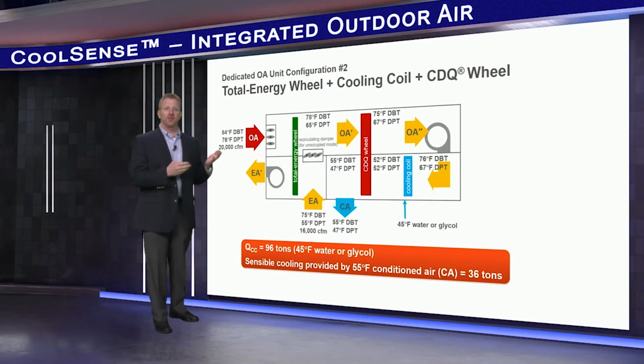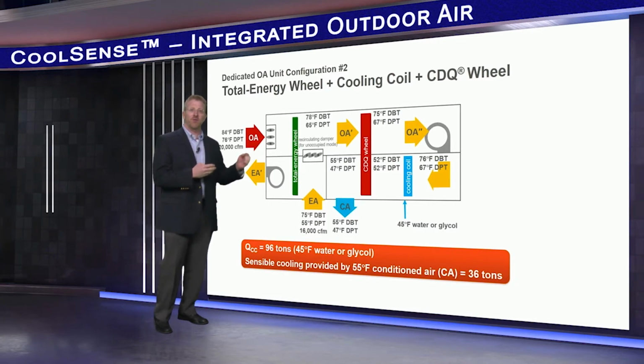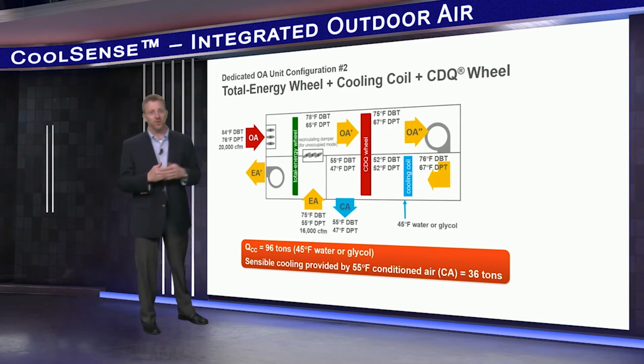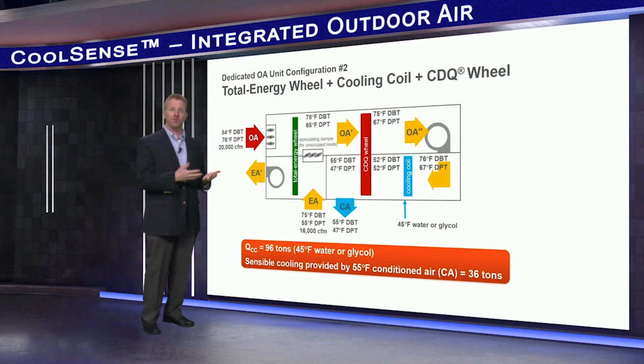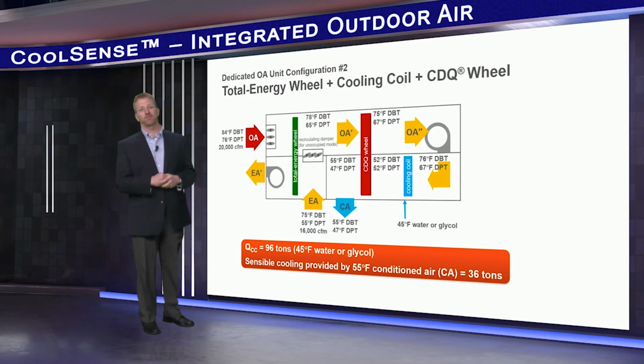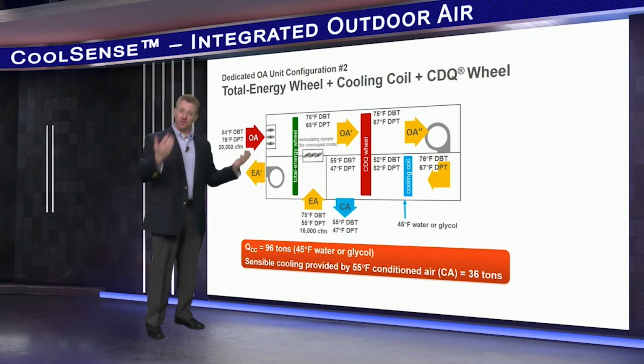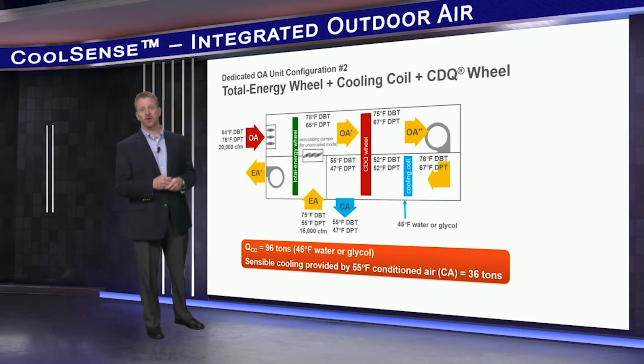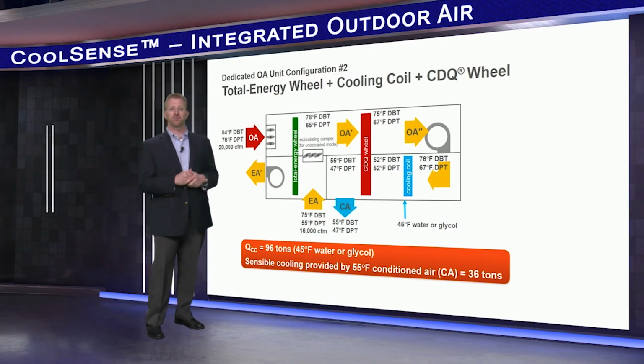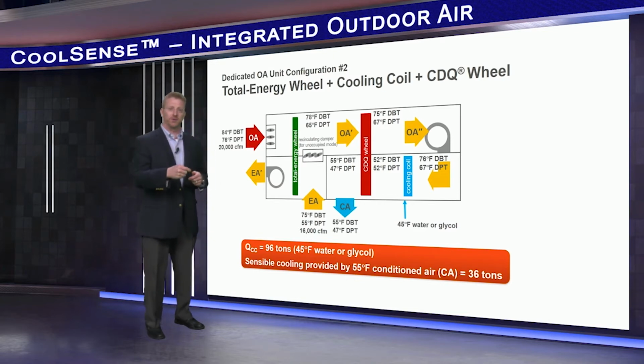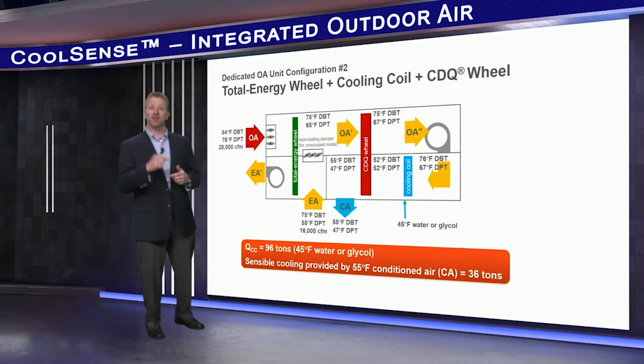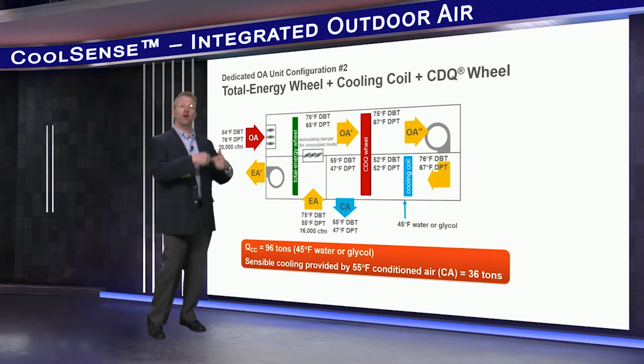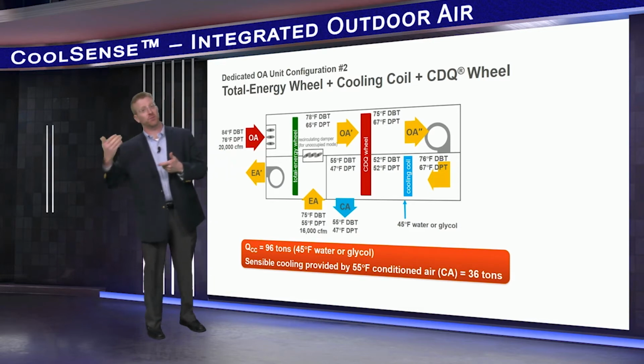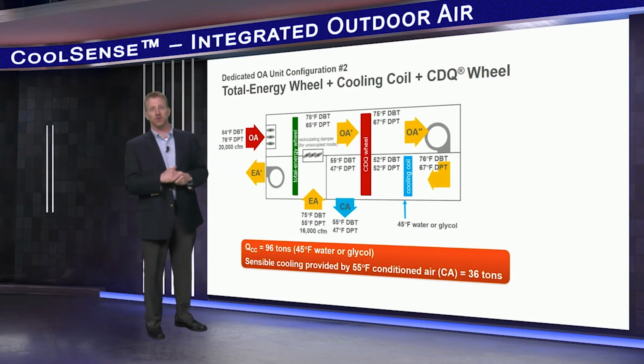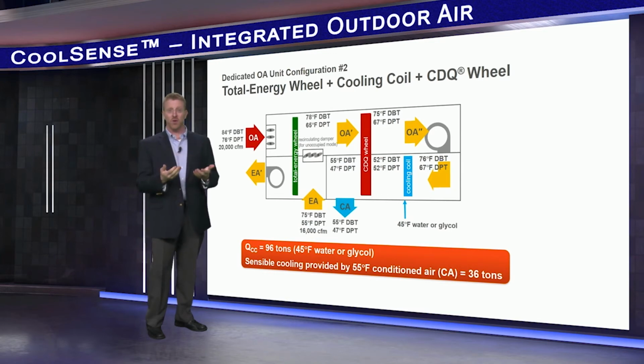Finally, notice that the leaving air dry bulb is now 55 degrees. For those engineers who are not comfortable sending 49 degrees down the ductwork, this might alleviate their concerns. There are some drawbacks, however. The desiccant wheel increases the physical size of the unit and adds pressure loss to the airstream, which does impact fan energy use. And by delivering warmer air to the CoolSense terminal units, it offsets less of the zone sensible cooling load, requiring the sensible coils to offset more of the space load. This might require larger coils in the terminal unit, a higher water flow rate, or both.